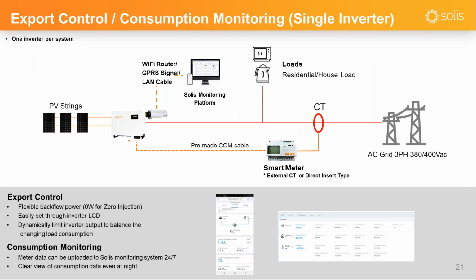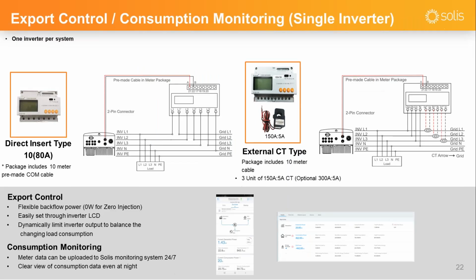Anyway, for the export power control and consumption monitoring purpose, it's pretty much the same. The three-phase inverters can connect to the three-phase smart meter for the export control and consumption monitoring. We can also provide two types: one is the external CT type, another is the direct insert type. And this model is used for a 380 or 400 volt three-phase system. And these are the two types of the meter.